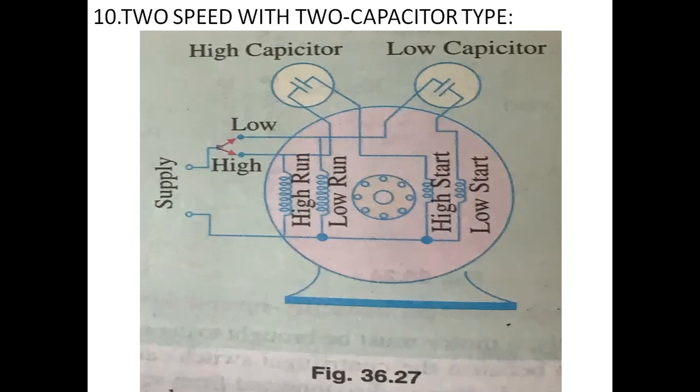These are the types of capacitor start motors. In all these ten types, capacitor start motors have the capacitor present only at the time of starting. By using a centrifugal switch, the capacitor is cut out when the induction motor runs to normal speed. Now, we will see what happens if the capacitor is kept in the circuit during running — that is called a capacitor start and run motor.